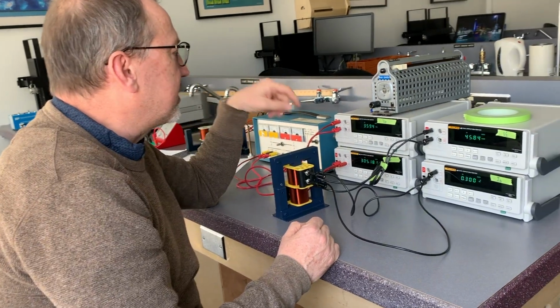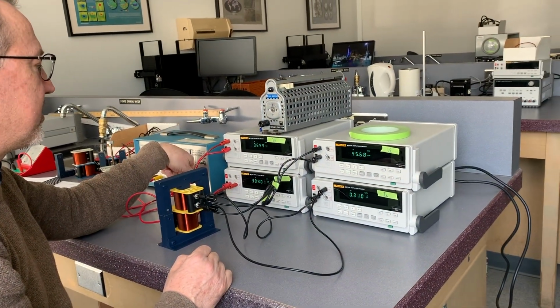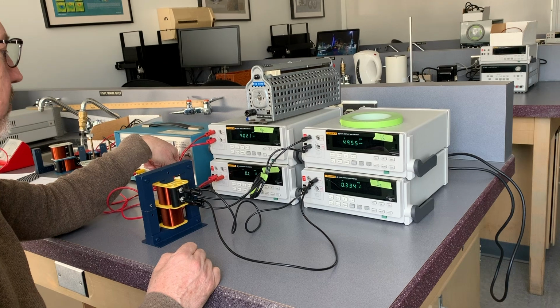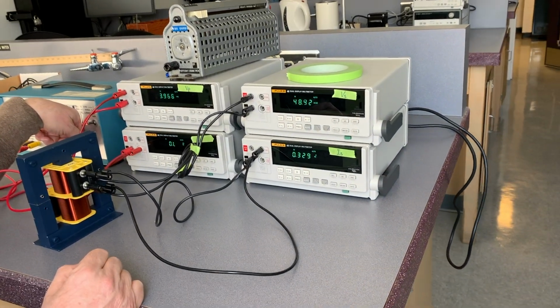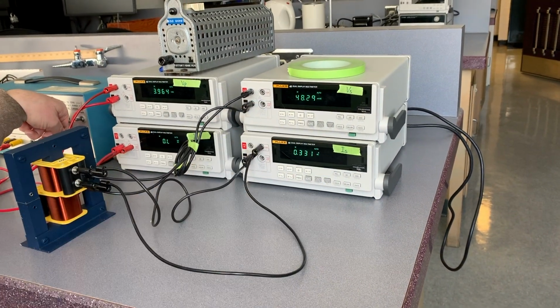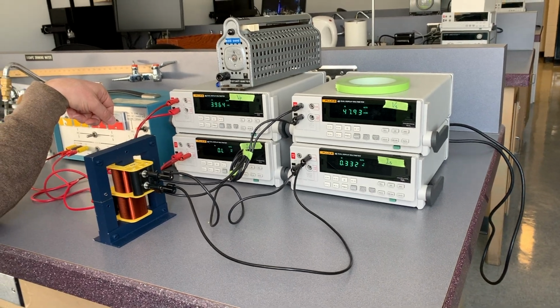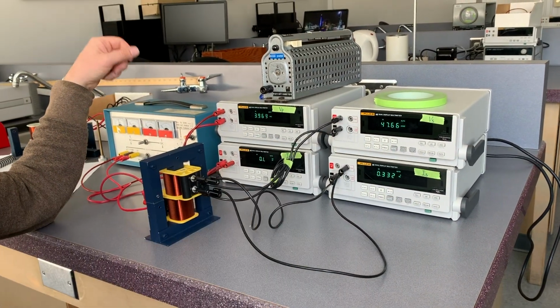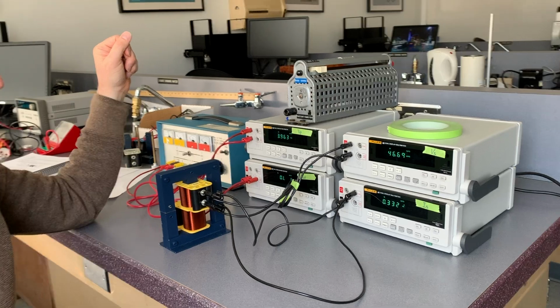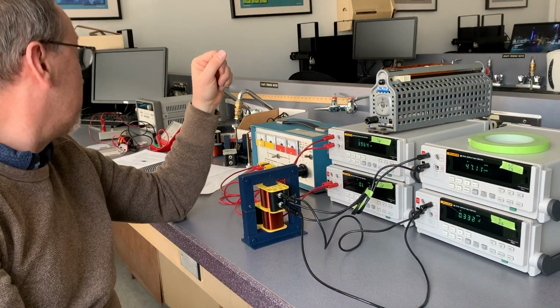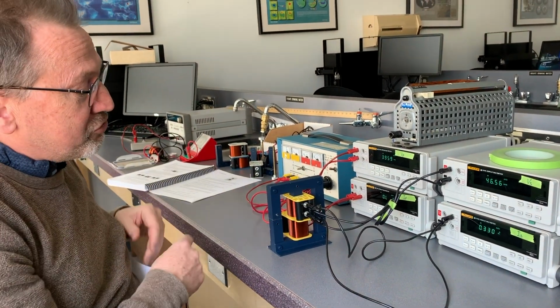Let's turn that back up to 4 volts. We have 4 volts on the primary, but the poor secondary has collapsed down to 48 millivolts. It's delivering a large current, but the voltage has collapsed, and this isn't the way you want to run a transformer.